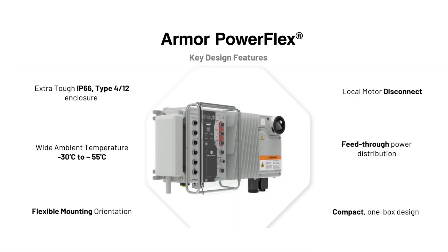The Armor PowerFlex is built in a NEMA 12 enclosure that has an IP66 rating for temperatures ranging from negative 30 to 55 degrees Celsius. The Armor PowerFlex is shock and vibration resistant and is capable of maintaining these ratings in various mounting orientations.